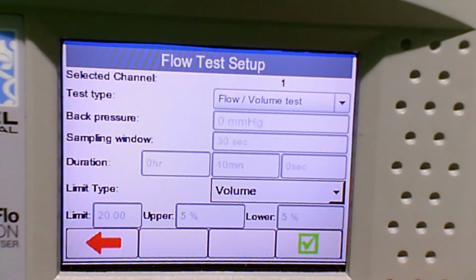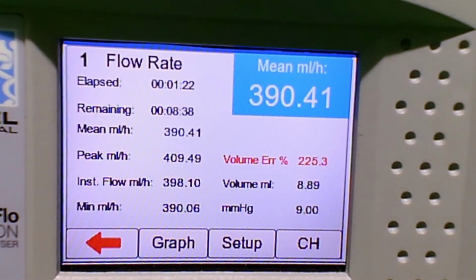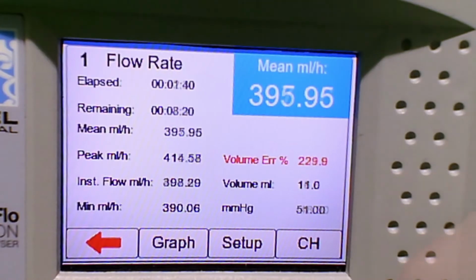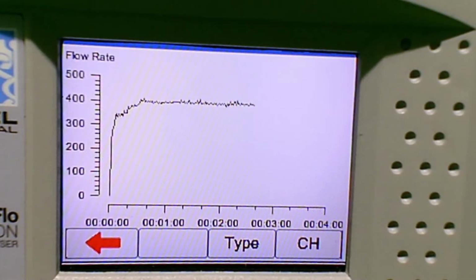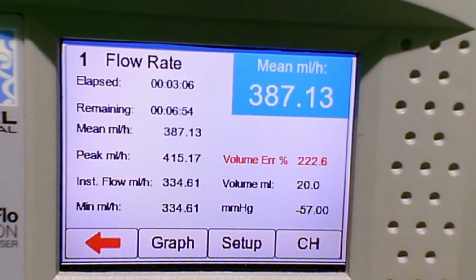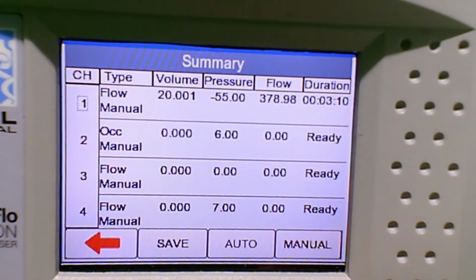But we're measuring volume here, so 20 mils. Volume to be infused is 20 mil. So we're just going to run through this test until it's complete. We didn't actually change the time, so we'll likely finish before the time's elapsed on the Multi-Flo. Okay, so we skip through to a few minutes in, and we can see now that the flow rate is starting to drift off, and these little peaks you can see, that's that peristaltic action from a volumetric pump. But over the 3 or 4 minute range, it will be accurate. At the moment we're just measuring the total volume infused, and that's common in PM schedules. You're just measuring the total volume over a certain time period.